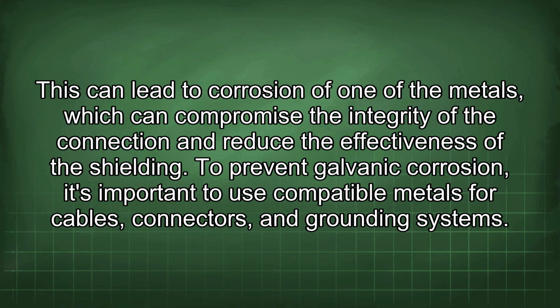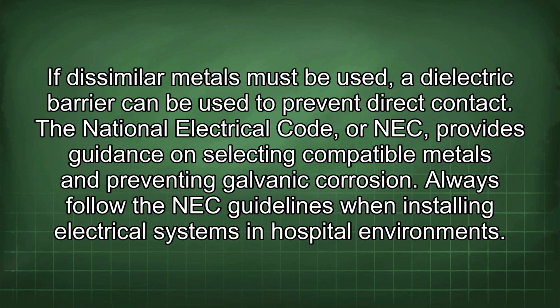To prevent galvanic corrosion, it's important to use compatible metals for cables, connectors, and grounding systems. If dissimilar metals must be used, a dielectric barrier can be used to prevent direct contact. The National Electrical Code, or NEC, provides guidance on selecting compatible metals and preventing galvanic corrosion. Always follow the NEC guidelines when installing electrical systems in hospital environments.